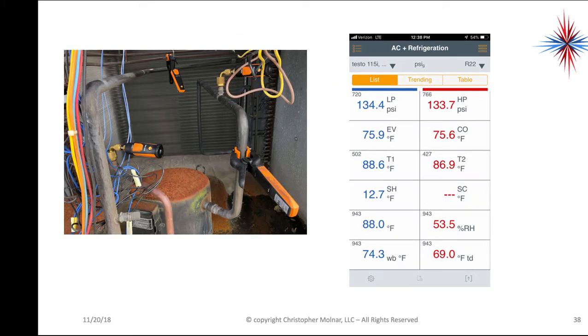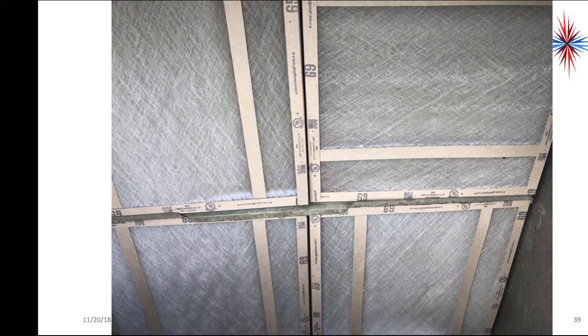Compressor 2, okay, we now have normal standing pressure for our temperatures, 134 psi, which tells me the condenser and evaporator is around 76 degrees. You know, can't argue with it. The inside building temperature and the outside, not in the sun, was about that. So I'm fine with that. It may end up being a little bit undercharged, but there's more problems here than that.